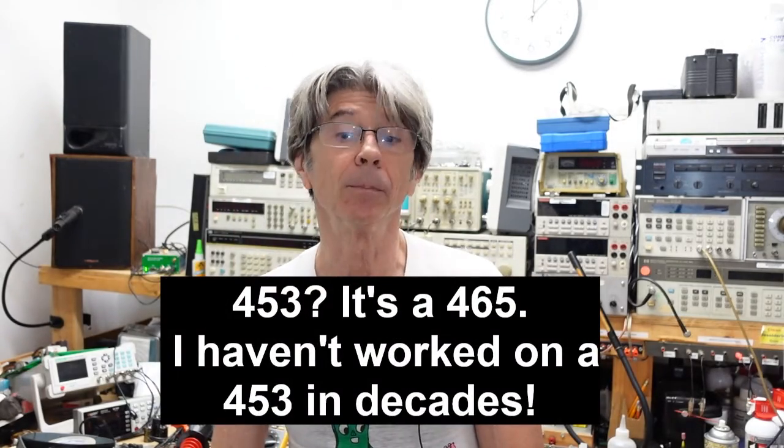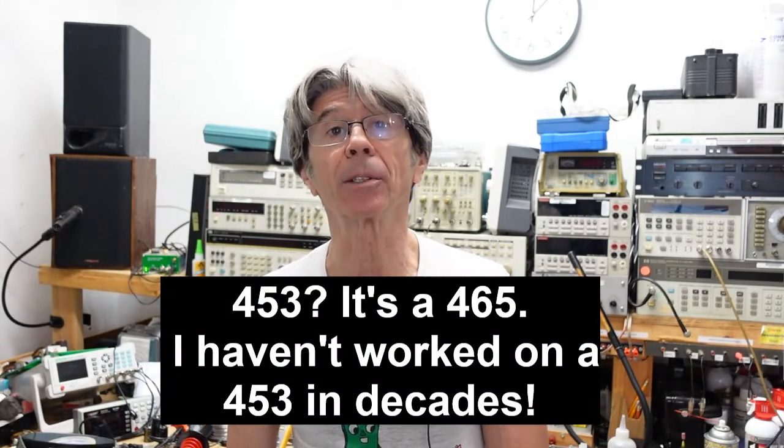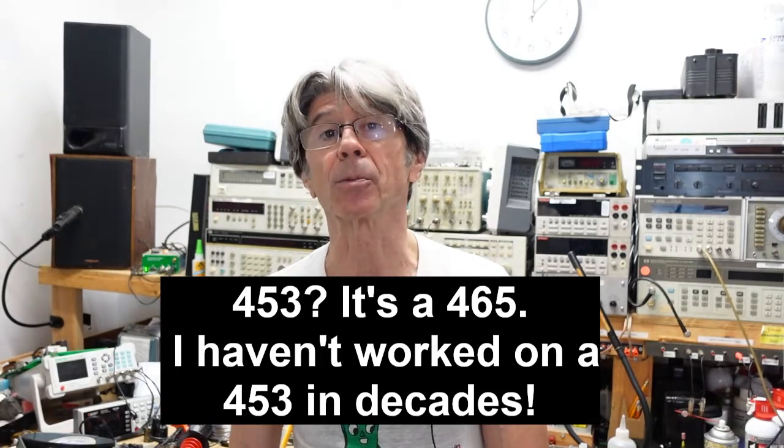Hi folks, I'm back and this is the conclusion of the video on repairing the Tektronix 465 scope. It turned out to have a bad bridge rectifier in the low voltage power supply, so we had no negative 8 volts and therefore no display.